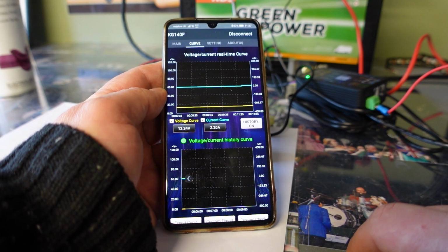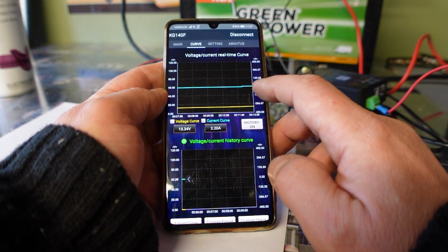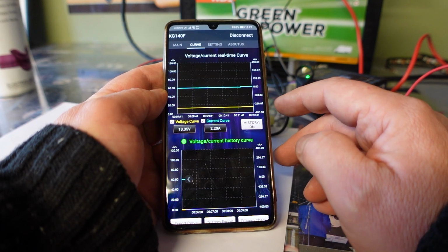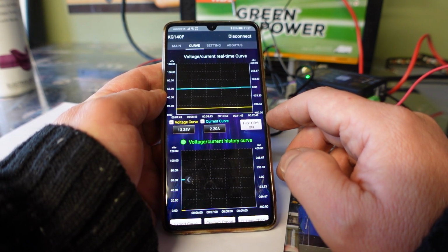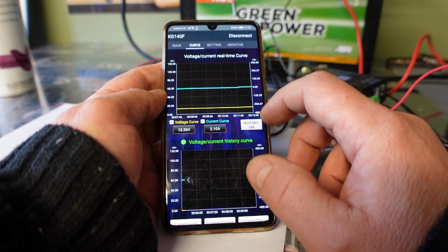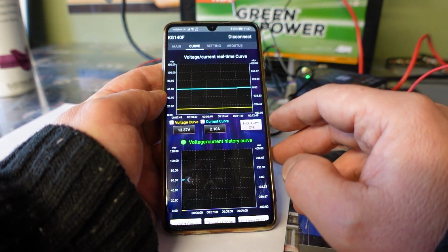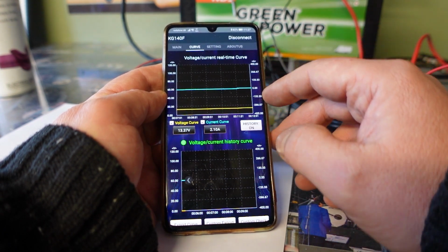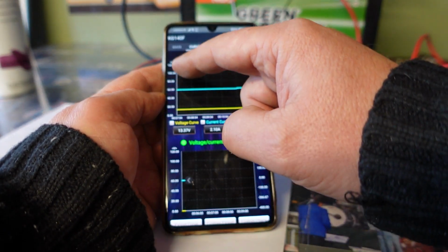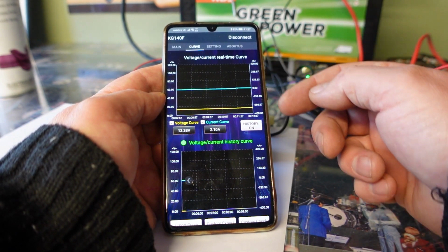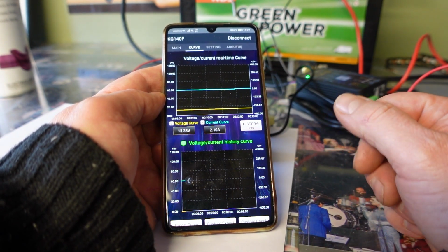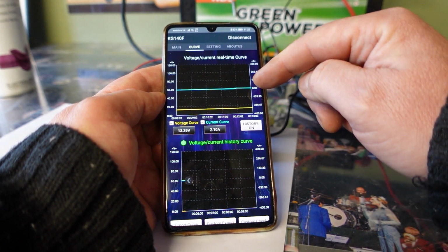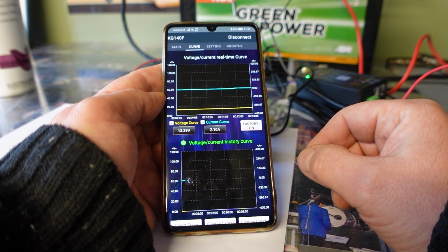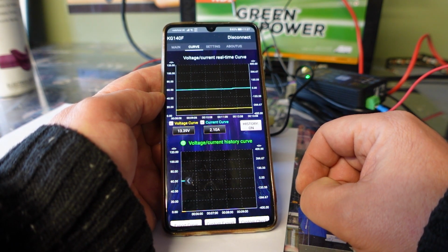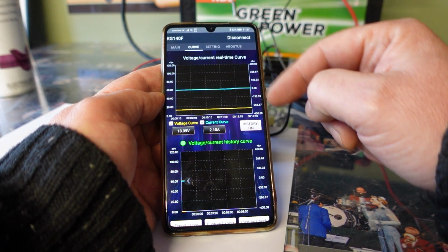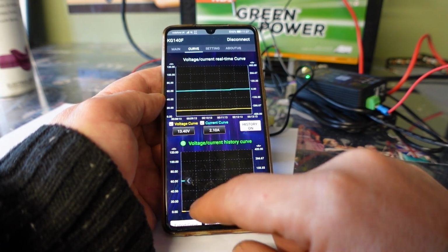Going to the curves, you can see on the current there's a slight flicker, probably where we switched the Victron on, and same with the voltage. The only thing I did notice with these graphs is that they're 0 to 400 on this side for current, and 0 to 120 volts on this side for voltage, and you can't change those parameters from what I can see, which is a bit of a shame really, because with small currents, like I'm only putting in 5 amps, and on some vans, my van, the maximum you'd probably put is 20 amps, having a 400 amp gauge isn't much help really.